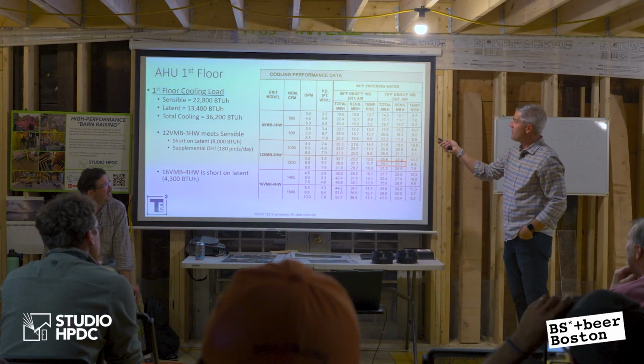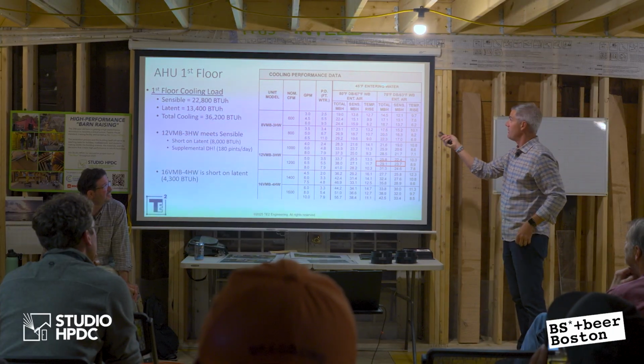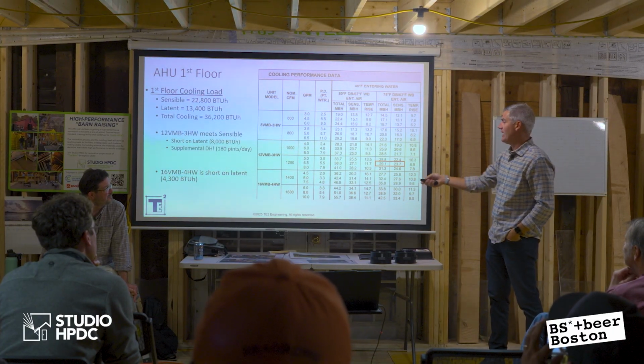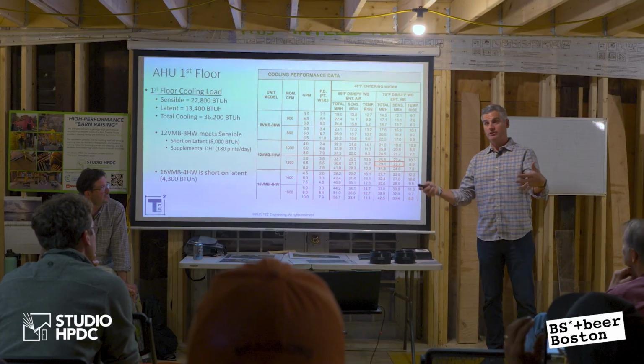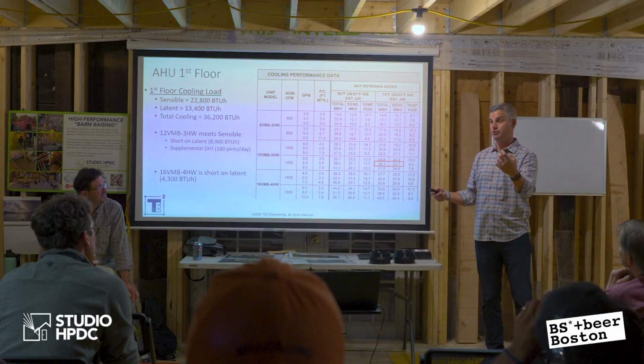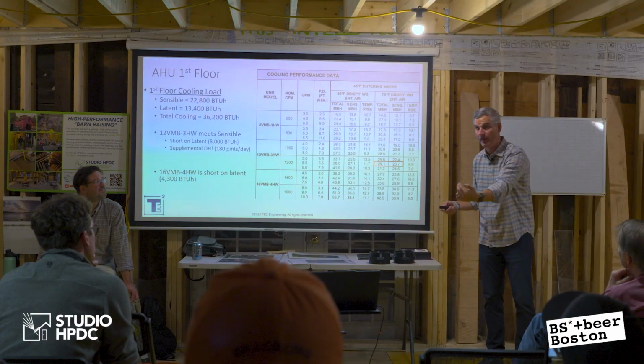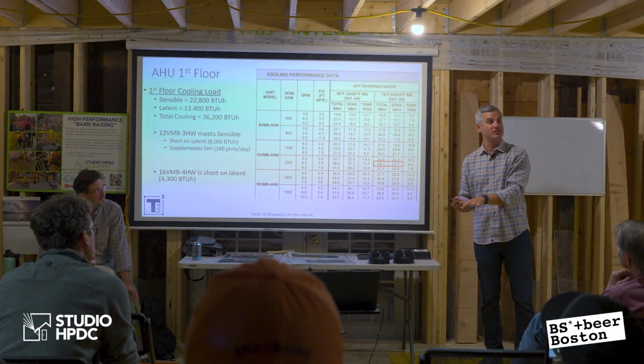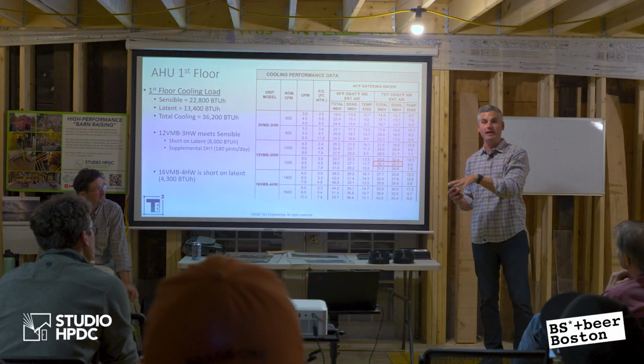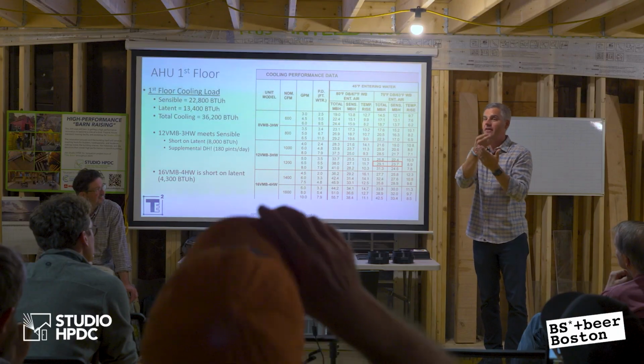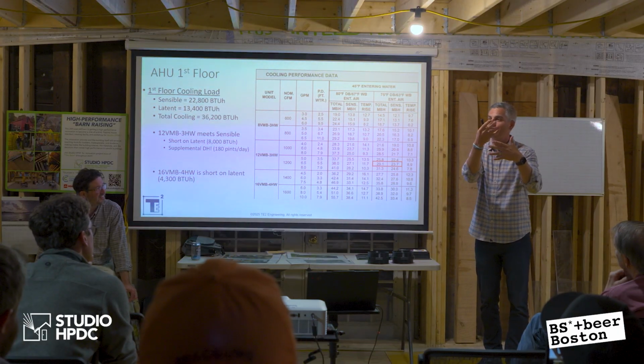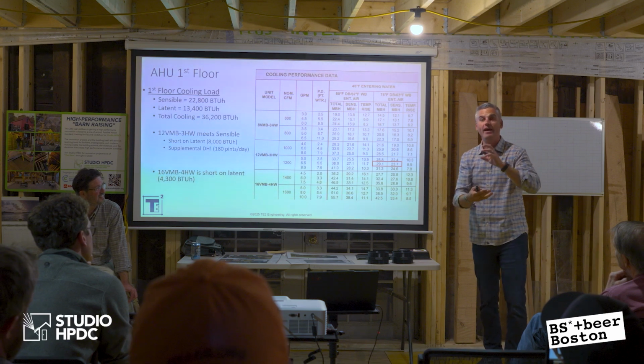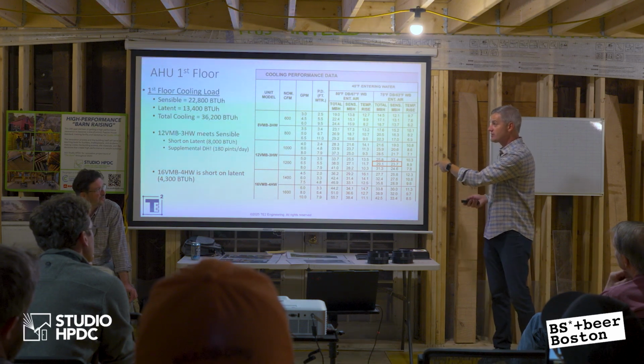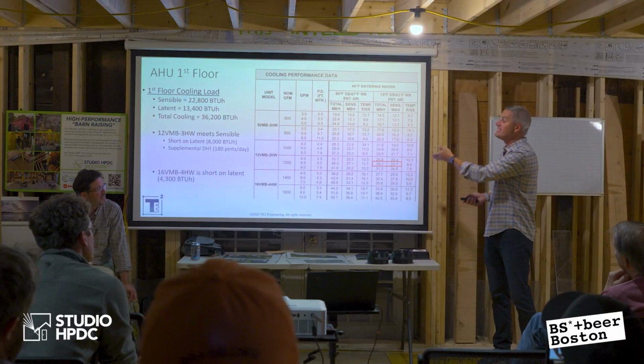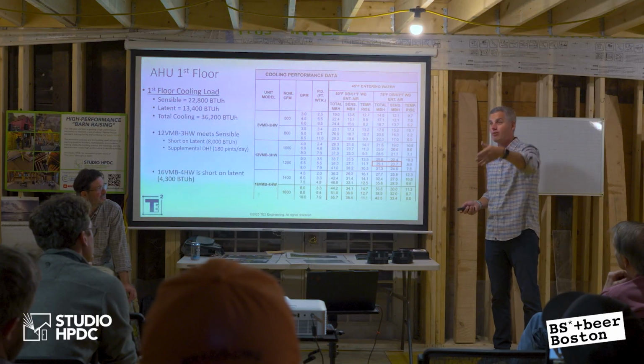So if you look at the capacity, if I look at 45 degree entering water temperature, and I could drop that by the way, but if I just look at that, what I can do is change the fan speeds. So I could put in a large box and run 45 degree chilled water through it, and I can change the flow rate through that coil, and I can drop the air handler speed. And by dropping the air handler speed, I'm allowing that air to go across that coil, and I give it more contact time. The air sits on that coil longer. It's a cold coil. It has a chance to actually wring out the moisture and dehumidify. So the sensible heat ratios on all of these products are 0.7, right, 0.75, even 0.65. I can do a Space Pak or a Unico, and I can get down to 0.6 sensible heat ratios.